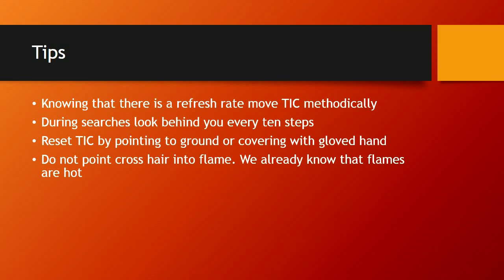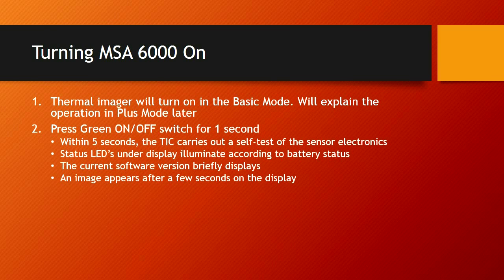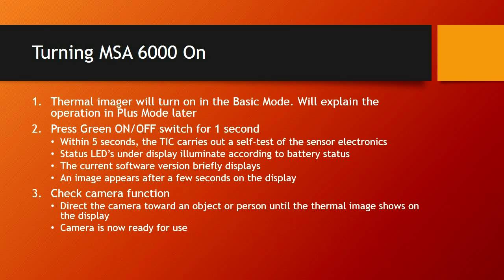To turn the camera on, the thermal imaging camera will turn on in basic mode. Hit the green button and hold it down — the camera comes on. Within 5 seconds of turning it on, the camera carries out a self-test of the sensor and electronics. Status LEDs under the display illuminate according to battery status. The current software version briefly displays, and the image appears after a few seconds. Check camera function by directing the camera toward an object or person — anything emitting heat — and the thermal imager should show a good image. The camera is now ready for use.